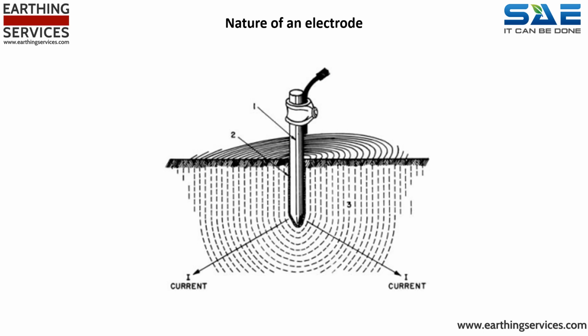Just a quick reminder on the nature of an electrode. Resistance to current through an earth electrode has 3 components. Number 1, resistance of the electrode itself and connections to it. Number 2, contact resistance between the electrode and the soil adjacent to it. And number 3, resistance of the surrounding earth. Other factors affecting performance are the total conductor footprint and the overall discharge zone and the conductor life cycle phase.